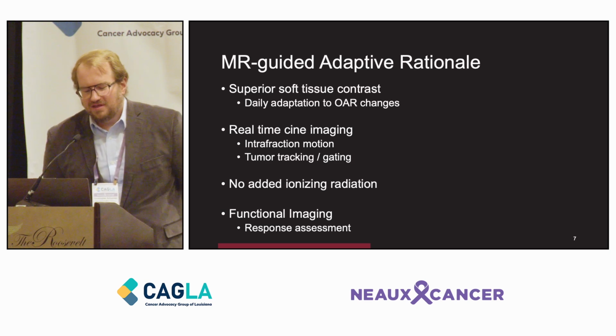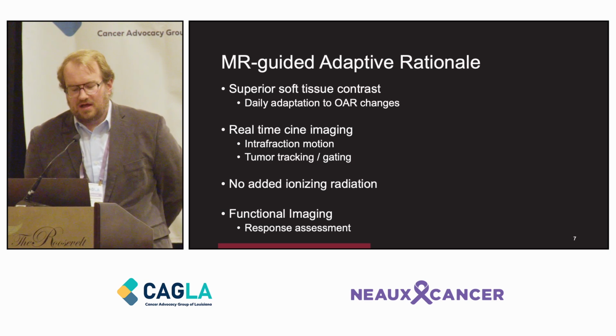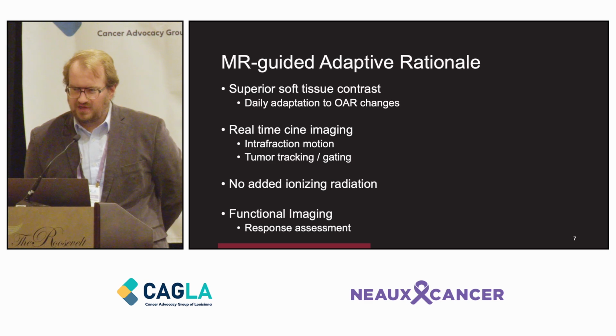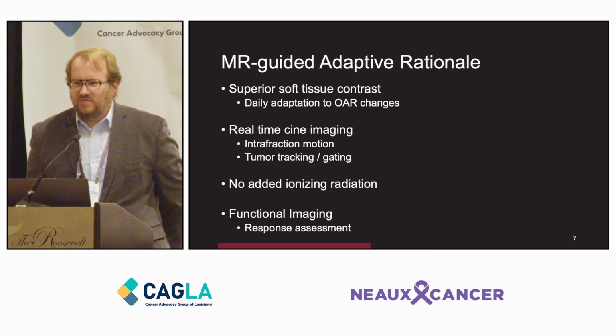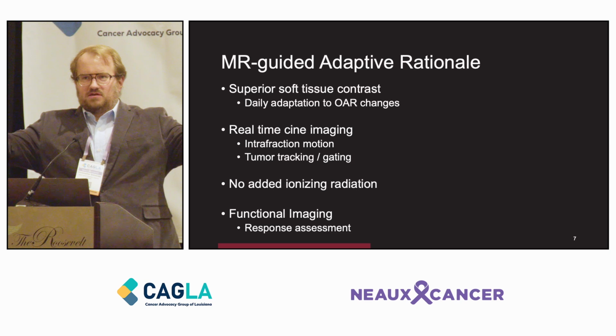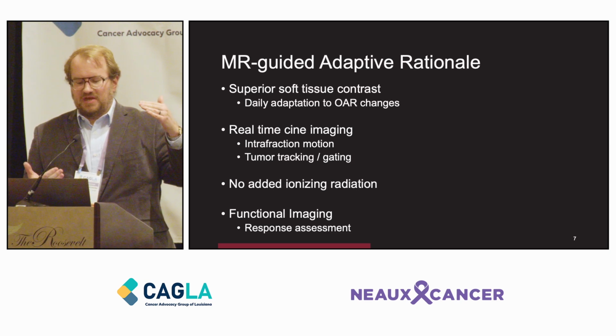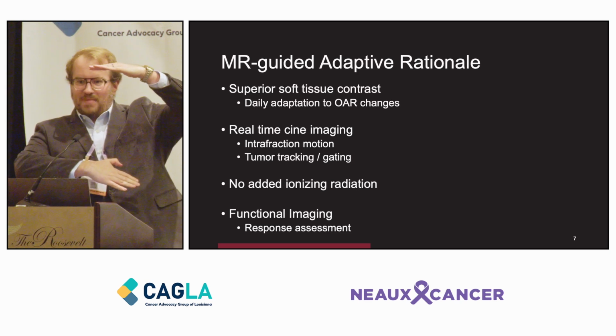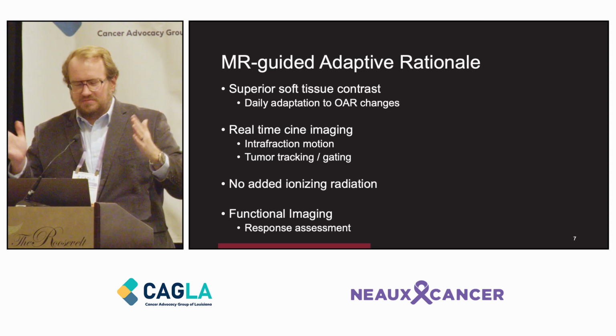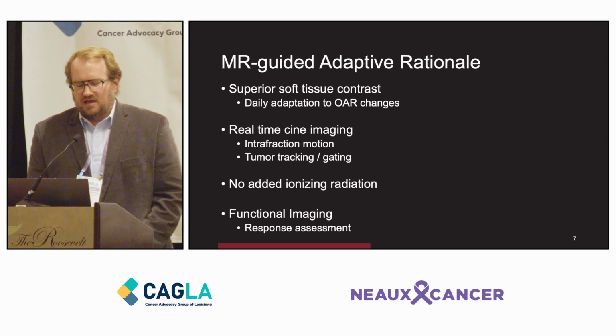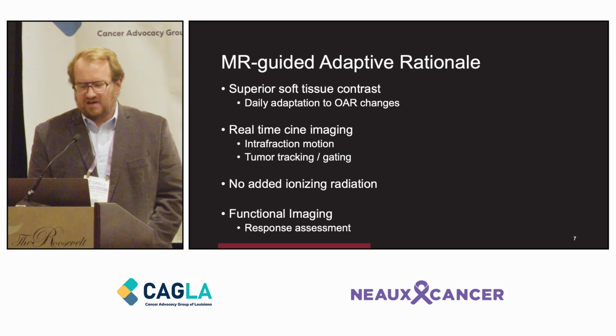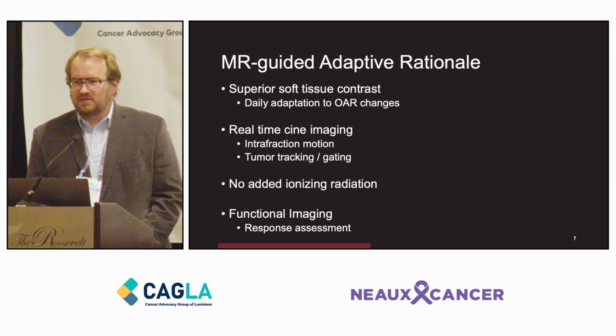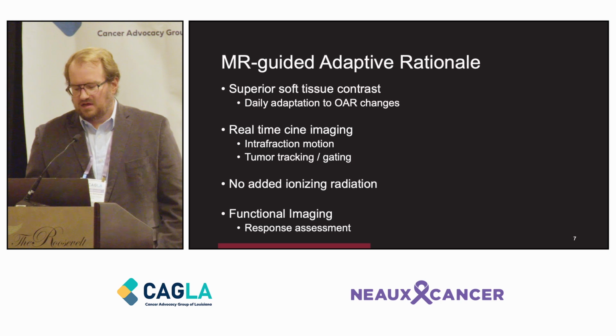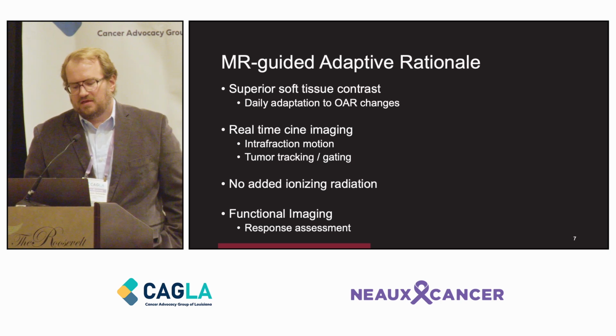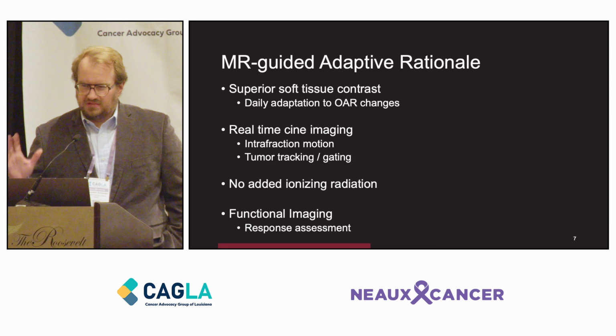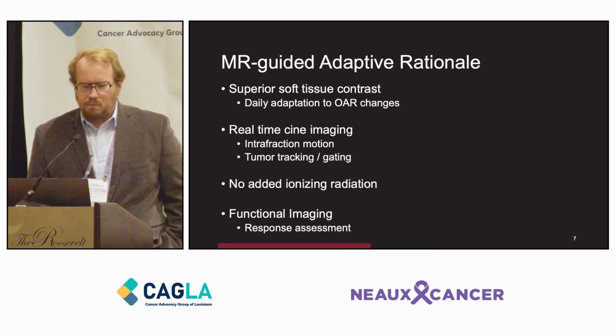more common. And then finally, there's a Canadian group, MagnetTx, I think is how they would pronounce it. They have the Aurora RT, which instead of being a conventional closed bore MRI, their system is based on a biplanar MRI with 2 flat magnets. That gives them the ability to do some different things. But it's also a low field MRI, 0.5 Tesla. So Elekta Unity is currently the only one on the market that's offering a 1.5 Tesla MRI linac combo, which allows them to do some things that their other machines can't.